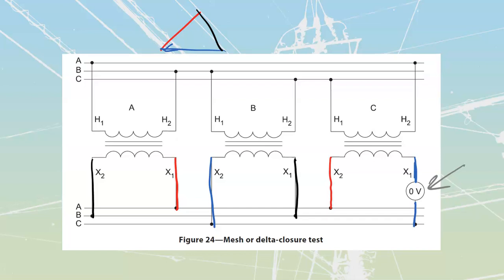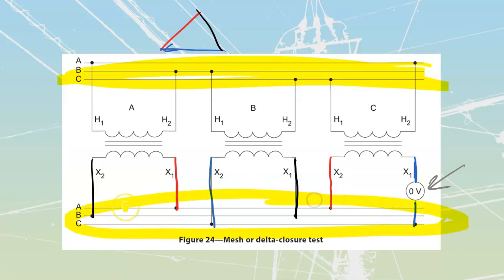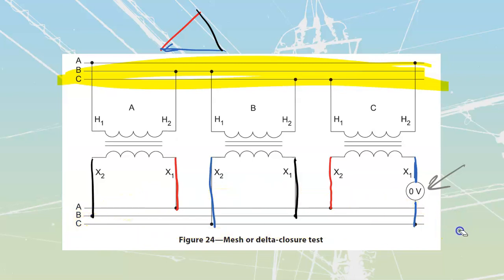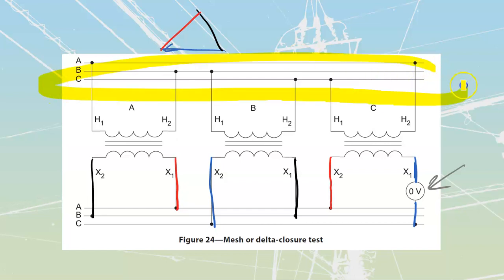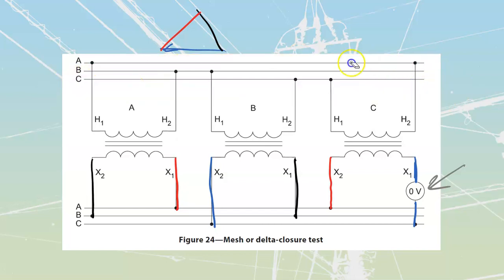I'm doing this on my secondary side, not exclusively on the low voltage or high voltage side - I'm doing it on the side that I'm supplying power. In this case, there was a high voltage bus existing and I was creating a low voltage system. But if I were creating a high voltage system using a step up, I would do the closure test on the high voltage side.